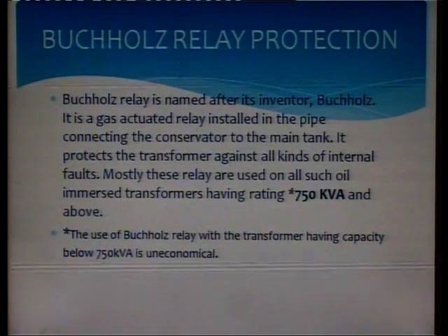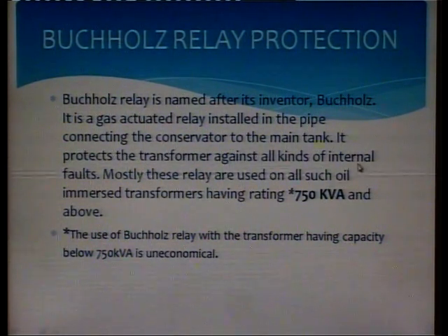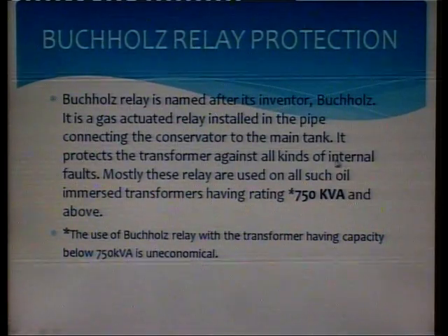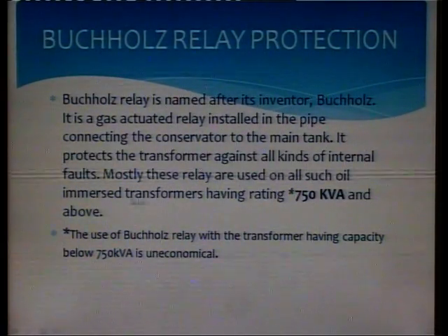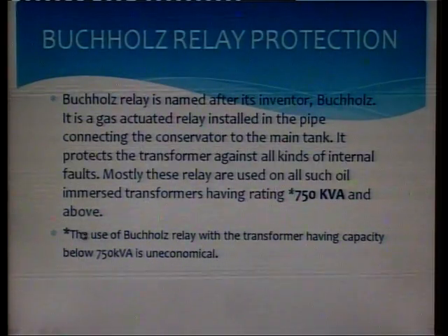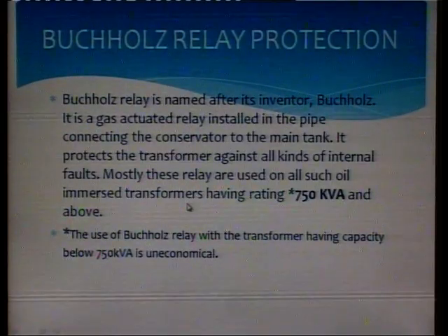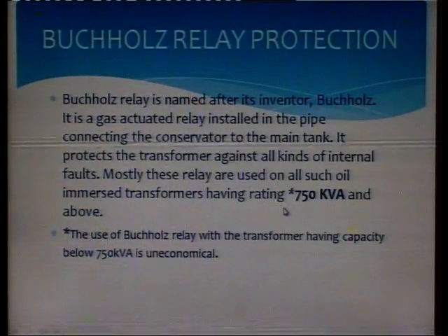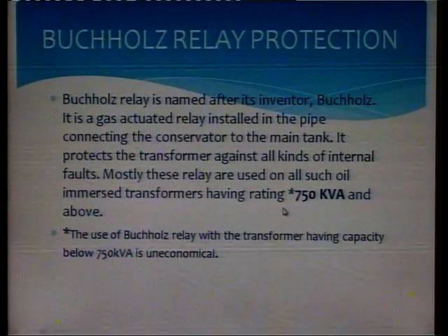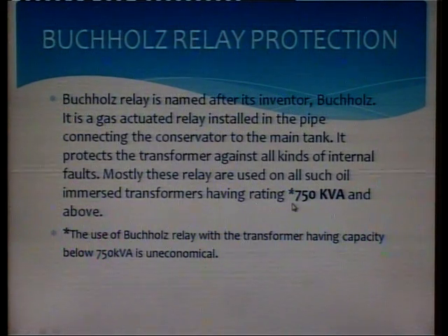So, it protects the transformer against all types of internal faults. Mostly these relays are used on all such oil immersed transformers having a rating of 750 kVA and above. This type of protection, the Buchholz relay protection, is only applicable for transformers having a rating of 750 kVA or above.